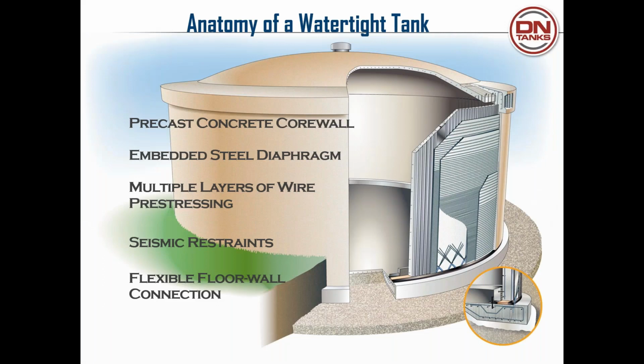It's also important that all of the tanks that are built are watertight, because there's chemical treatment in chilled water systems. There's usually a biocide and a rust inhibitor in small concentrations within chilled water. We don't want that type of chemical to be leaking out. So all of our tanks are built watertight.